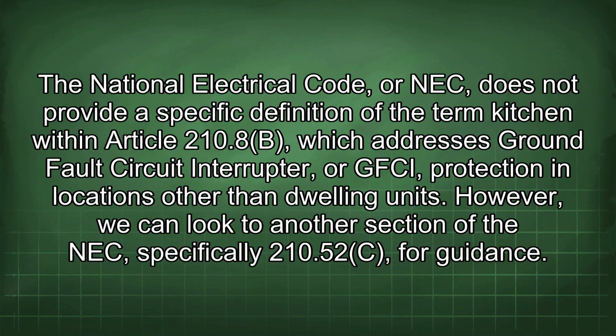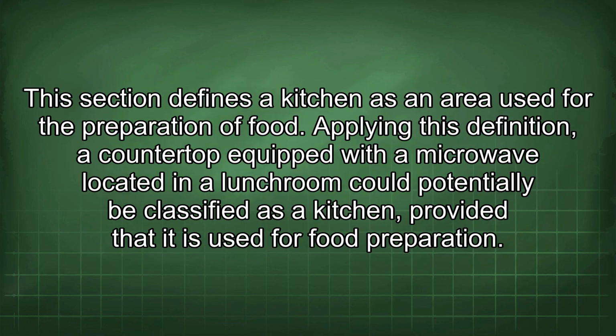The National Electrical Code, or NEC, does not provide a specific definition of the term kitchen within Article 210.8(B), which addresses ground fault circuit interrupter, or GFCI, protection in locations other than dwelling units. However, we can look to another section of the NEC, specifically 210.52(C), for guidance. This section defines a kitchen as an area used for the preparation of food. Applying this definition, a countertop equipped with a microwave located in a lunchroom could potentially be classified as a kitchen, provided that it is used for food preparation.